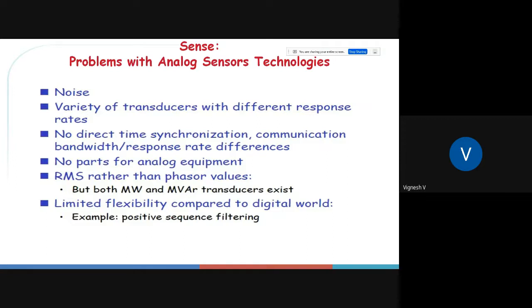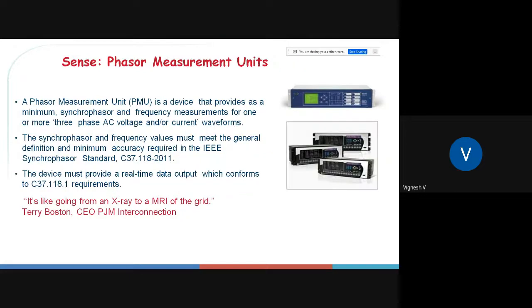For example, and above all, the analog sensors have limited flexibility compared to the digital counterpart. One typical example is that it has positive sequence data, so you can get positive sequence data directly from the PMU values. Yes, next slide please.